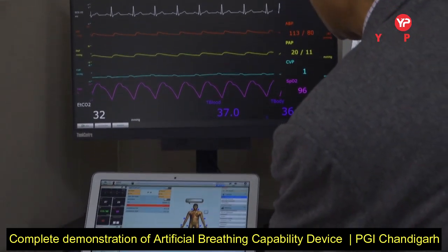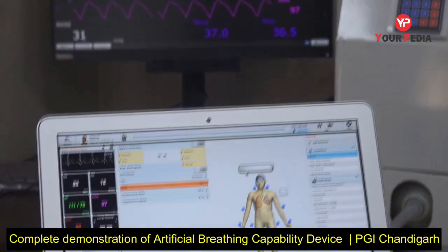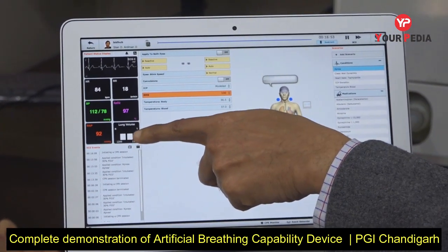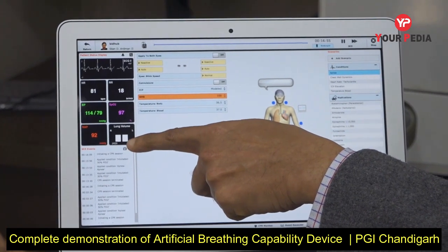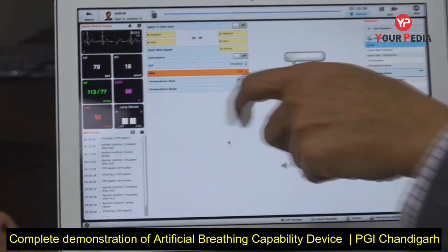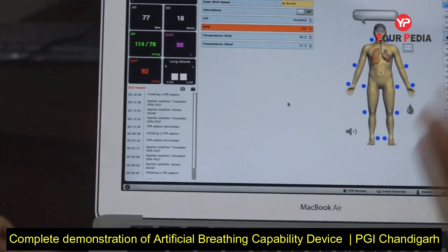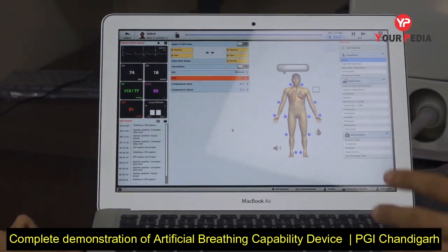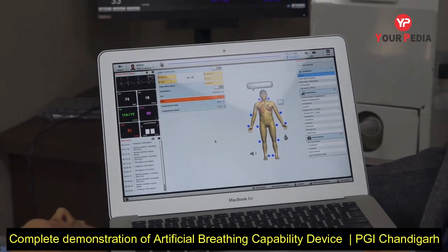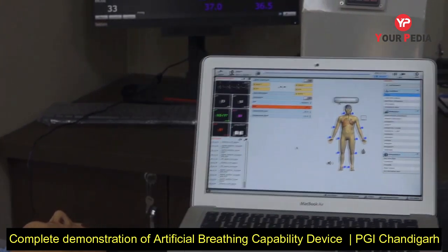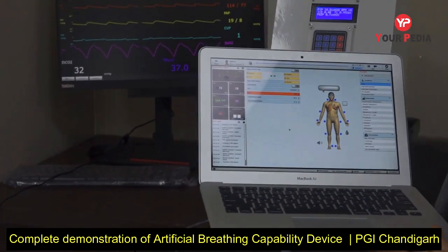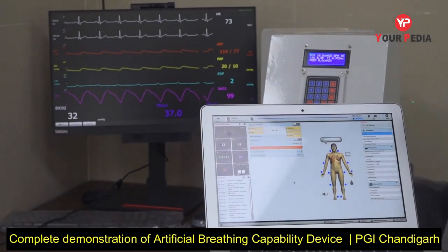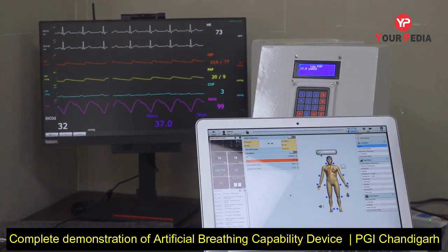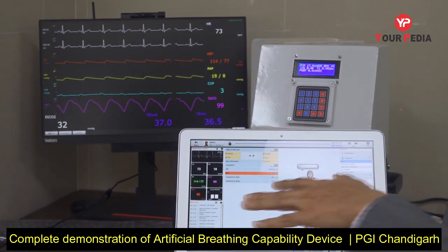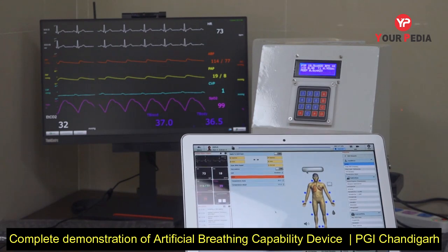In addition to this, we can also see that this little device here is showing us the actual volumes which are going into the two lungs. So from the baseline of about 1150, this is reaching about 1400 mils in each lung. That's about 250 ml of air being delivered to the right lung and an equal amount to the left lung. So that's about 500 milliliters of volume being delivered in a typical tidal fashion. This was a simulation to show that the patient now seems to be stable. He has achieved his vital parameters, the saturation is back to normal, the end tidal CO2s are in the acceptable range, and the volumes being delivered are also acceptable.